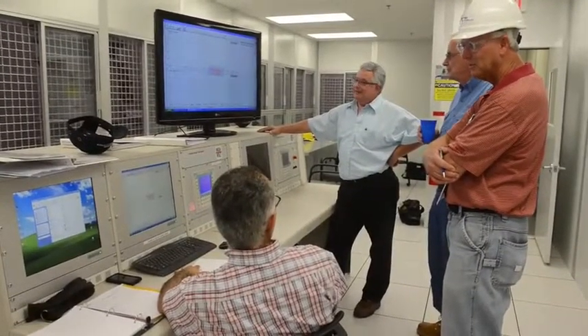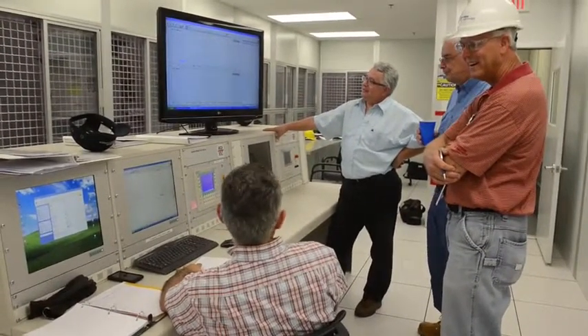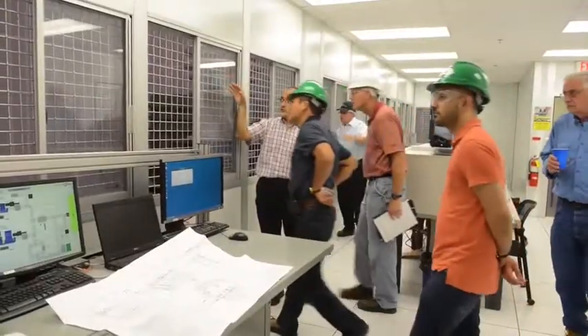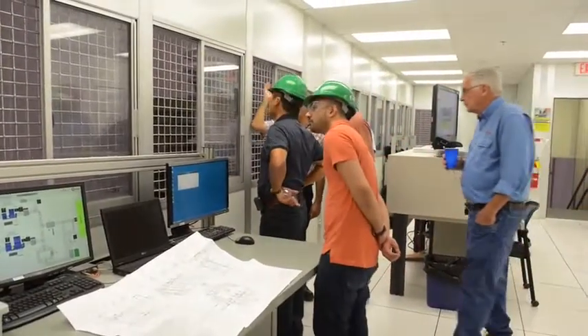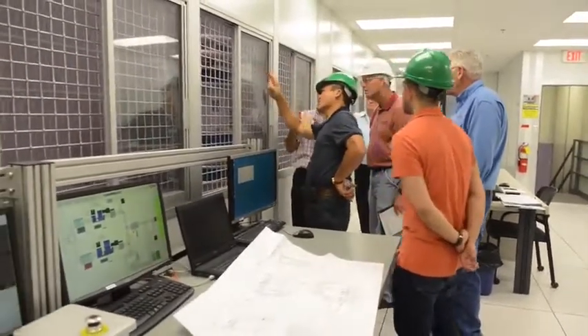A state-of-the-art impulse generator made by a high voltage company based in Germany uses remote digital controls that are fully operated from a console located in a sealed controlled cabin. Twelve 200 kV sections give this generator the capability to test up to 2400 kV BIL with 365 kilojoules of energy. We have already tested a 1650 kV BIL transformer using this equipment.